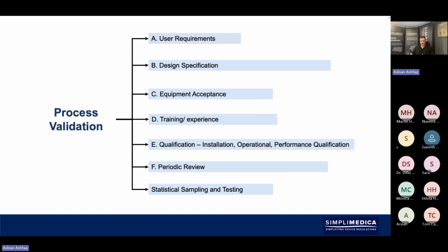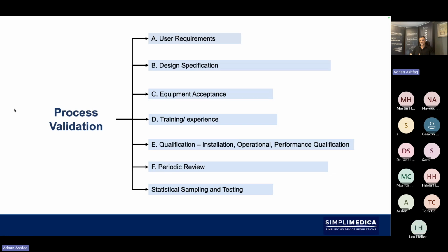So importantly, looking at the schematic, it's to look at user requirements, which then allow us to design the machine, which will then ultimately lead towards some level of equipment acceptance, where there are tests that will be performed. There's an important element of training and experience that's required when these validations are being performed and when the equipment is being validated. We need to go through the motions of qualification, which is, as we said before, IQ, OQ, PQ: installation qualification, operational qualification, and performance qualification. Once the qualification is completed, a validation summary report should be written up to complete the validation and to state that everything has been accepted.